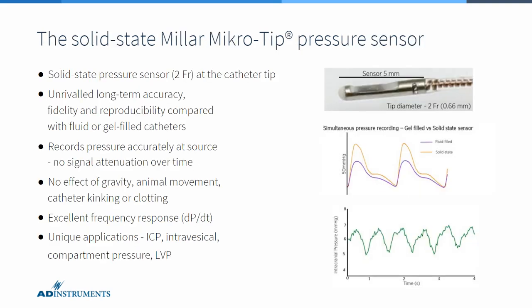So I mentioned that the rat pressure telemeters incorporate the Millar Mikro-Tip pressure sensor, which is a solid state pressure sensor, 2 French diameter, which is 0.6 millimeters, located at the catheter tip. This technology offers unrivaled long-term accuracy, fidelity, and reproducibility compared with gel or fluid-filled catheters.